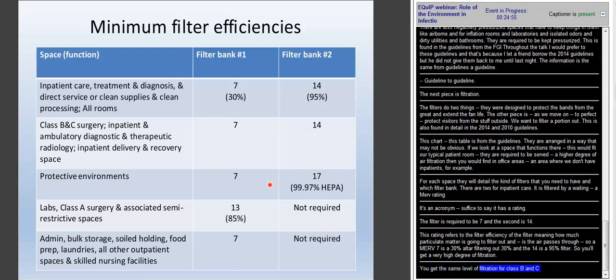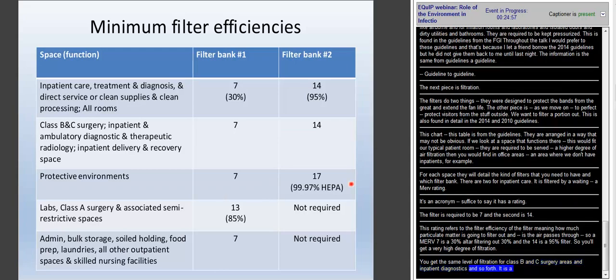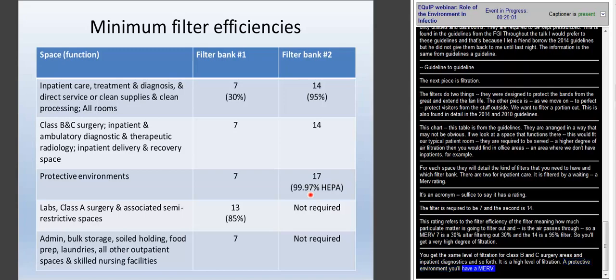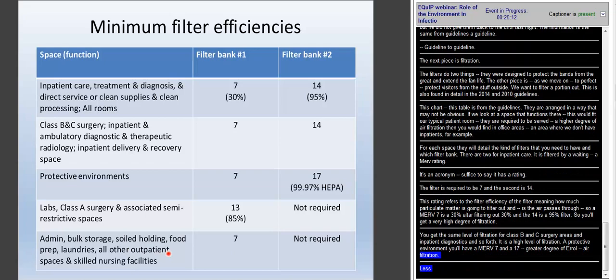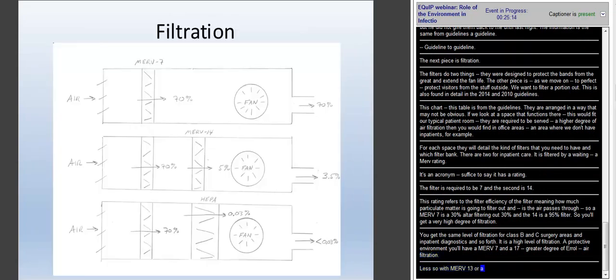In protective environments, you'll have a MERV 7 pre-filter and a HEPA filter, a MERV 17 on the terminal end, which is an even greater degree of air filtration. Less so for labs with a MERV 13, which is an 85% filter, or a single MERV 7 for admin type areas. So how does this work?